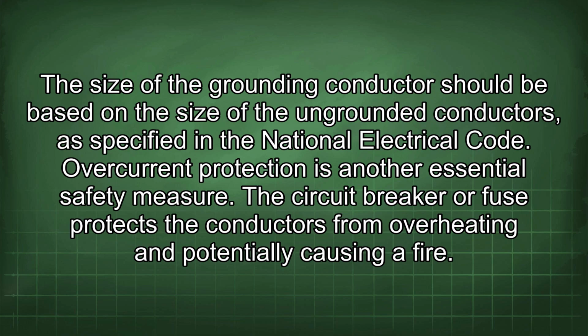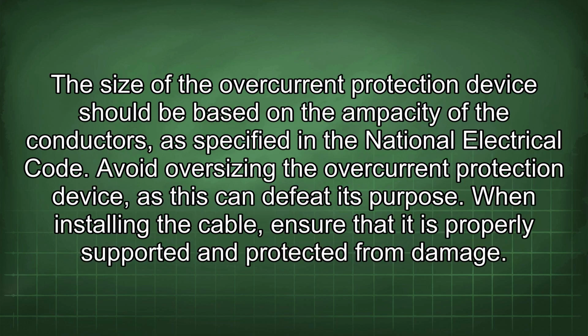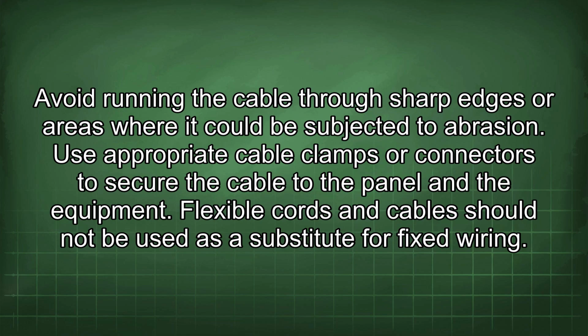Overcurrent protection is another essential safety measure. The circuit breaker or fuse protects the conductors from overheating and potentially causing a fire. The size of the overcurrent protection device should be based on the ampacity of the conductors, as specified in the National Electrical Code. Avoid oversizing the overcurrent protection device, as this can defeat its purpose. When installing the cable, ensure that it is properly supported and protected from damage. Avoid running the cable through sharp edges or areas where it could be subjected to abrasion. Use appropriate cable clamps or connectors to secure the cable to the panel and the equipment.